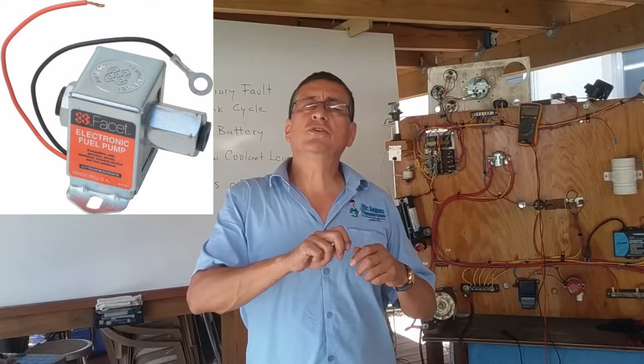If my generator is gasoline, the only thing you need to verify is the transfer pump. Is the transfer pump running? You disconnect the output of the transfer pump. You have the transfer pump on the screen right now, this is the output, and this is the input where fuel comes from the fuel tank. It's simple: you activate the pump directly with a couple of alligator cables on the positive and negative, and verify if the pump is pumping fuel.